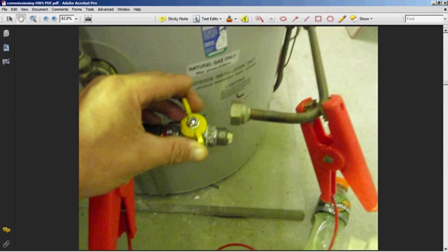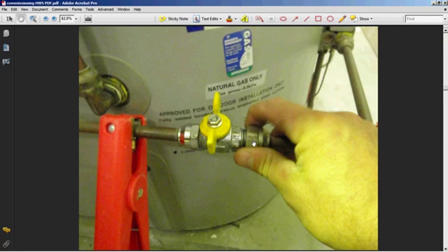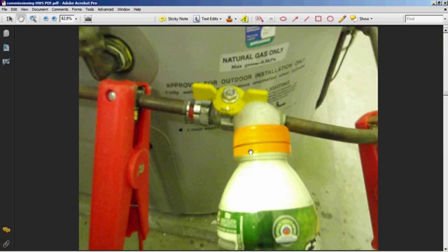You only need to turn the valve on slightly just to blow the air gas mixture out and any swarf that is in there. Rejoin the gas valve. And as soon as you've done that, make sure you turn the gas valve back on and you bubble test the join. If you don't do this, it could leak, and it will leak till there's no other chance of testing it. So if it leaks, it will leak till it blows up a house.